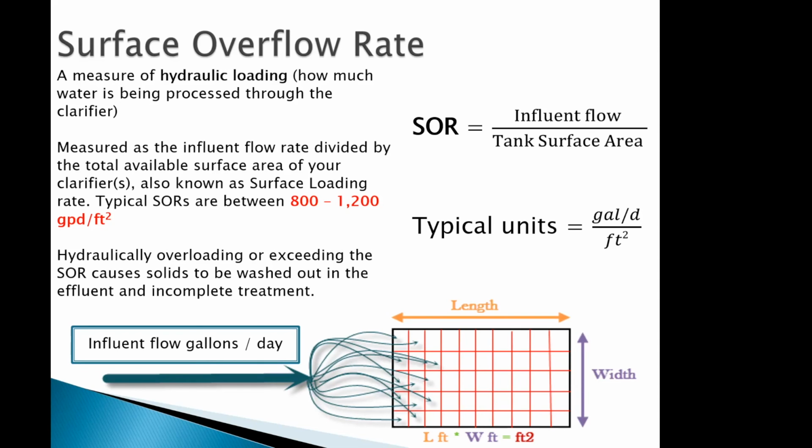So if you have, say, 4 or 5 primary clarifiers, you might take some of those clarifiers offline in the summer, say, for maintenance, right? We don't need all these tanks, the flows are lower, but you might hit a point where your surface overflow rate starts pushing up against the upper limit of how hard we want to push a clarifier. And so as the plant operator, your job is going to be to understand when it is appropriate to put on that next tank and basically divide the flow between more tanks. And that'll decrease your surface overflow rate in each one. Okay, does that make sense?